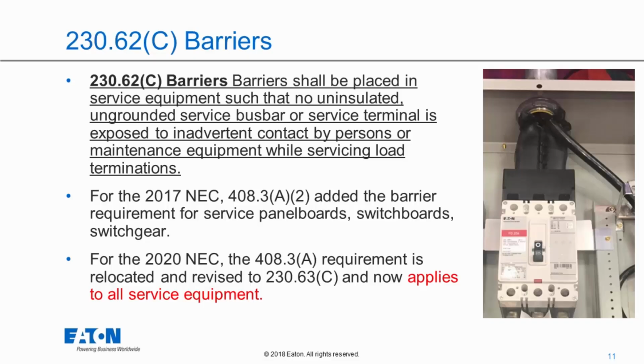We have a picture there on the right. This appears to be perhaps a panelboard, and the breaker there is the main. What you can see is they have some line side terminal covers to prevent any access to the line side terminals, and they also have what we call a boot, if you will, to prevent further access to those service conductors.